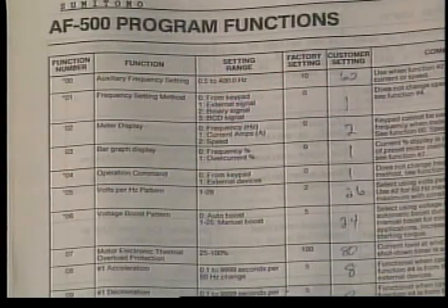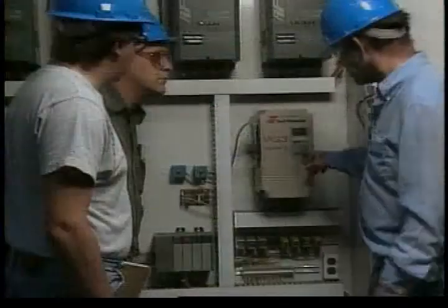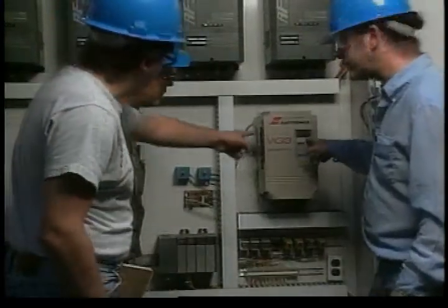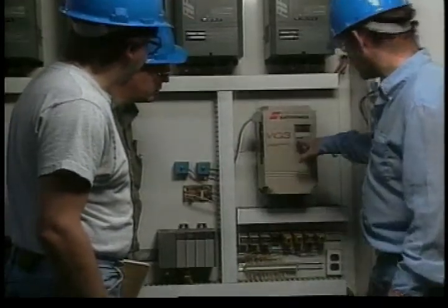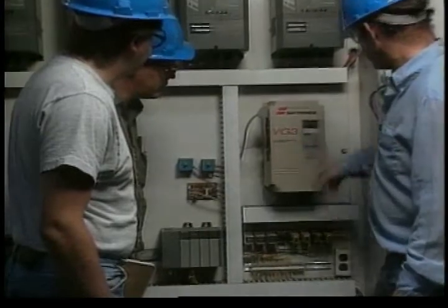These settings are usually programmed into the inverter when it is installed. However, if the application has changed very recently, the inverter may not have been reprogrammed and tested adequately for the new application, or someone may have made unauthorized changes in the programming. When an inverter has developed an internal problem, it will have to be repaired or replaced.